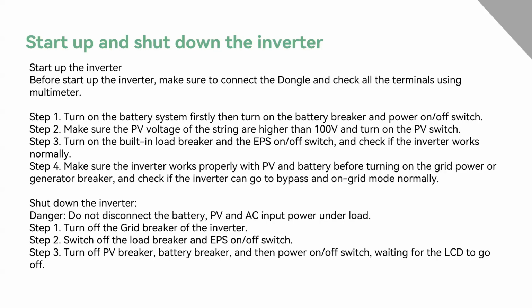And after that, when we shut down the inverters, we have to make sure that there are no actual loads connected when we disconnect the battery, the PV, and the AC input power. Okay, so step one is to turn off the grid breakers of the inverters. Step two is to switch off the load breakers and the EPS on or off switch. And step three is to turn off the PV breakers, the battery breakers, and the power on switch. And then the SNA inverter will be turned off.